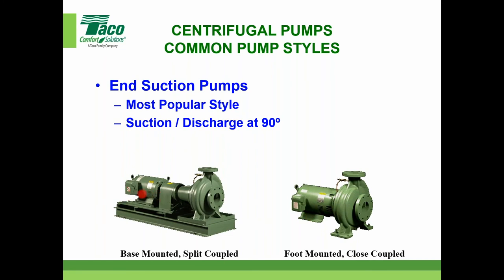These split coupled pumps, you don't have to take the motor off. You may have to unbolt it and twist it out of the way so you can have access to move the shaft back. But nonetheless, you do not have to disassemble the motor and lift it out of place. So that's one thing that split couples have going for them.